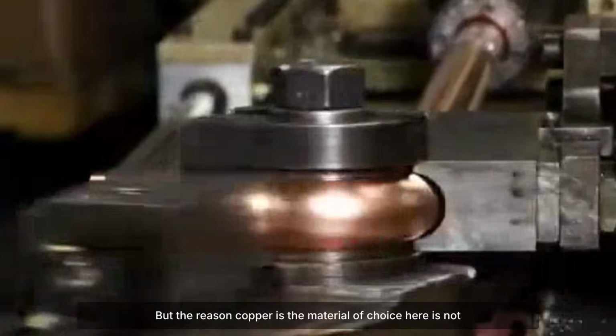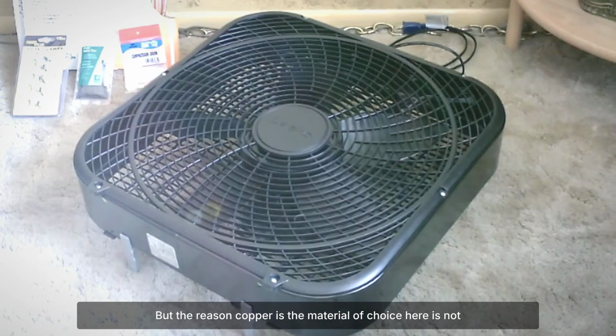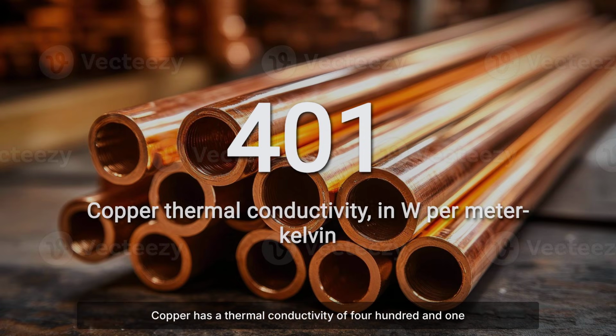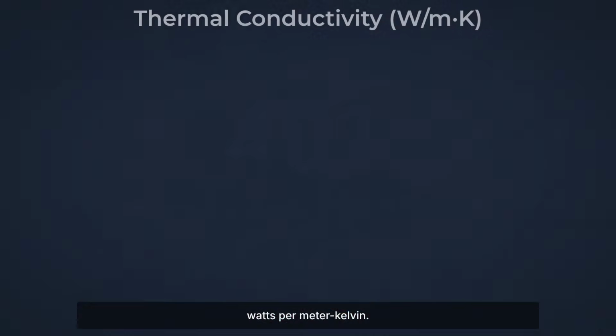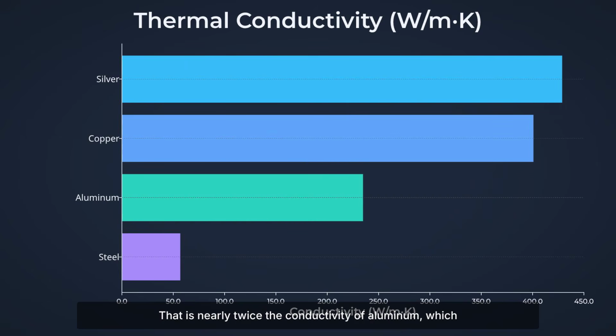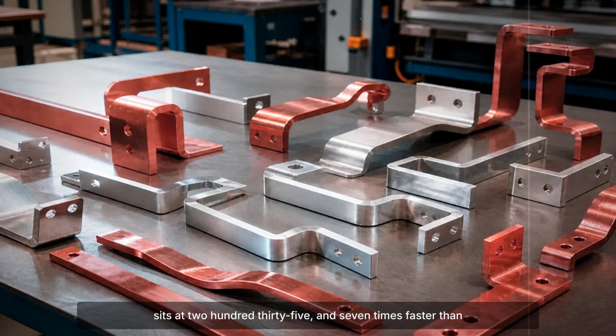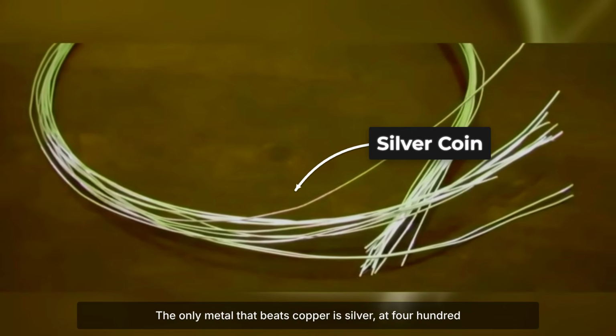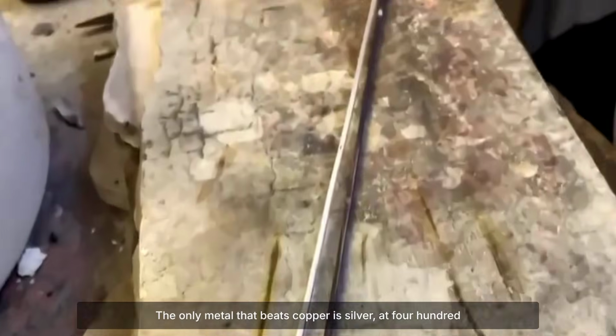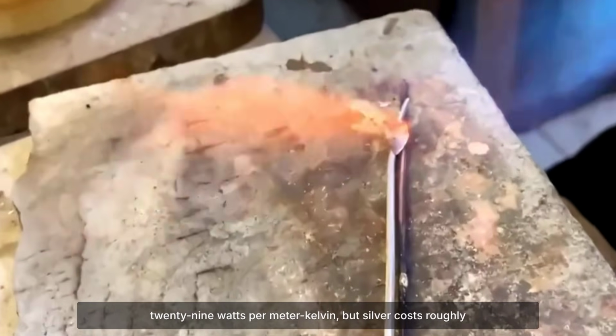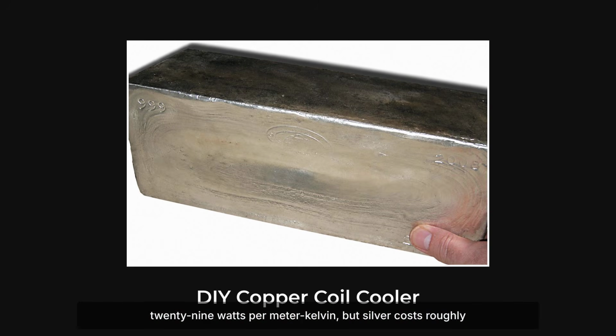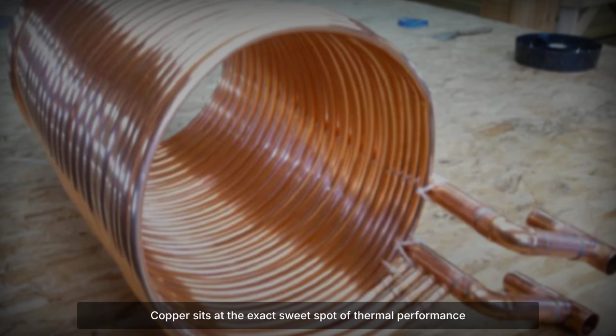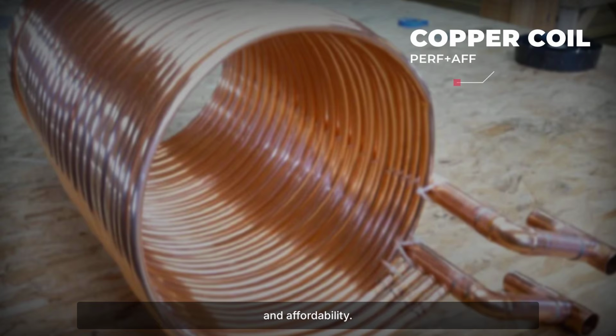But the reason copper is the material of choice here is not arbitrary. Copper has a thermal conductivity of 401 watts per meter Kelvin. That is nearly twice the conductivity of aluminum, which sits at 235, and 7 times faster than steel. The only metal that beats copper is silver, at 429 watts per meter Kelvin, but silver costs roughly 50 times more. Copper sits at the exact sweet spot of thermal performance and affordability.